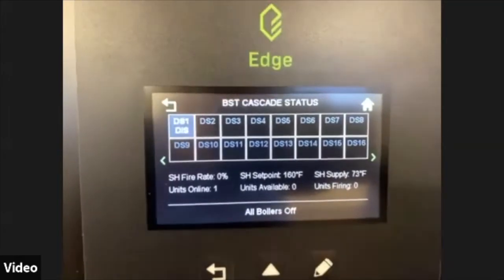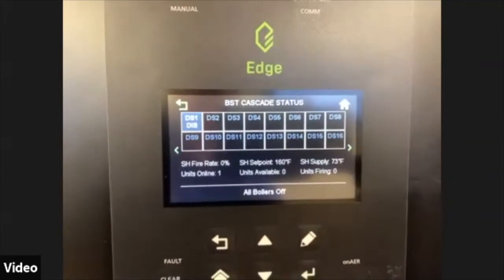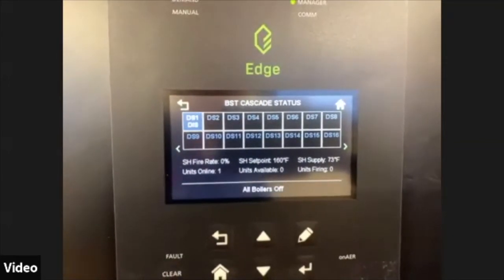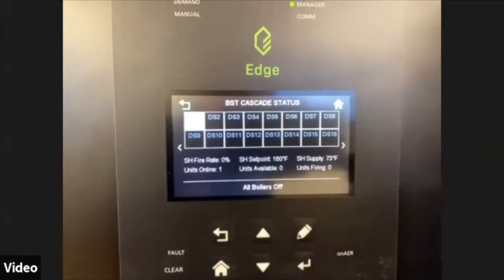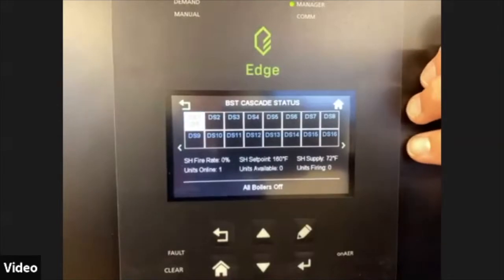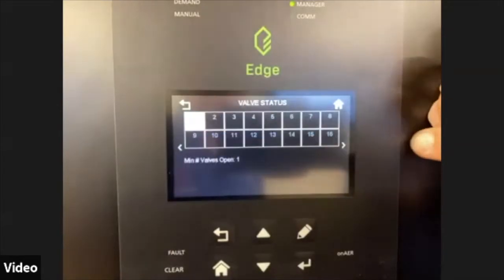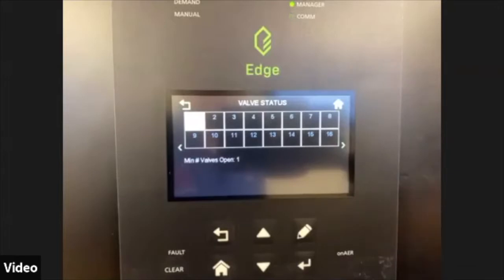But it would populate every one of those squares, and it would let you know whether it's disabled, whether it's in alarm, whether it's on standby. So you can get a good overview of what each boiler is doing right from this one screen if you have up to 16 boilers. We go over again. This is a secondary screen to that screen.